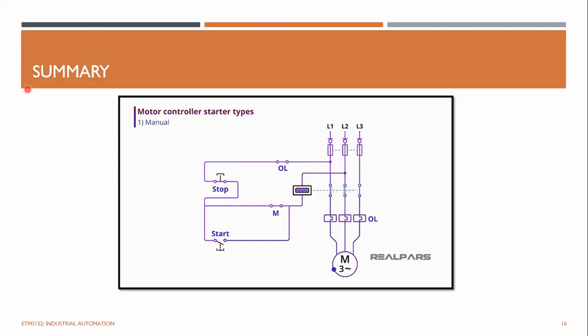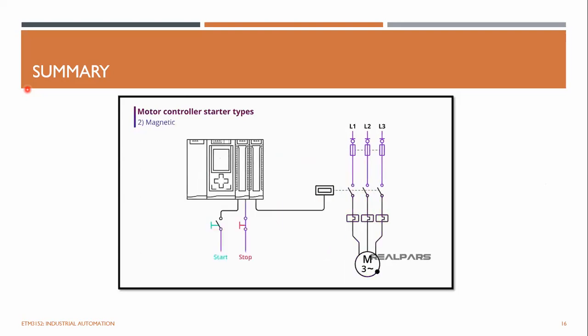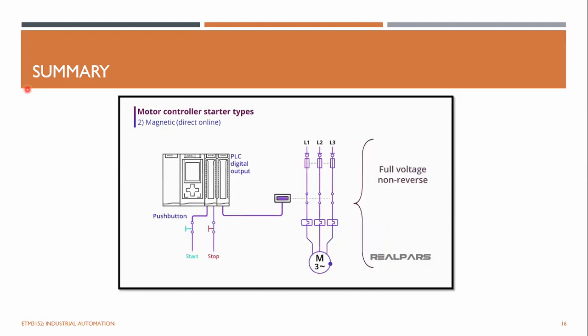off. Due to safety considerations, manual motor starting is limited to motors of 10 horsepower or less, but they can be used on single or with three-phase applications. Magnetic motor starters, or direct online starters, are the most common single-speed starter type. For magnetic starters, a PLC digital output, a push button, or a selector switch is used to pull in a coil, which magnetically holds the starter contacts closed, allowing current to pass to the motor. Magnetic motor starters are used with FVNR and full voltage reversible motor controllers.